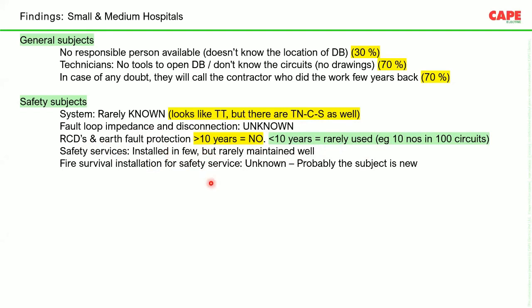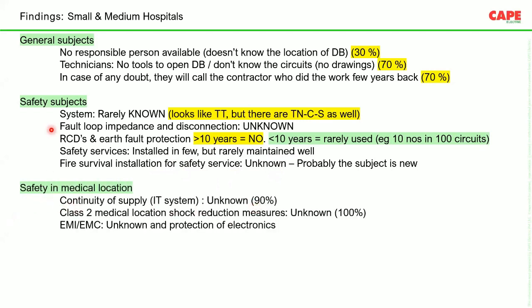Safety services, meaning the installed systems for firefighting or emergency, are installed, but not maintained well. Most often they are not in working condition. Fire survival installation is very rare. This first part, the safety subjects which I have shown, is for the general electrical installation, whereas for the medical location, let's say group 1 or group 2 medical location, where continuity of supply is necessary, in most cases this subject is unfortunately mostly unknown. For group 2 medical locations, the shock reduction measures are very, very rarely known. One of the subjects here is supplementary equipotential bonding. I will explain it later. And subjects like EMI and EMC are very much unknown.